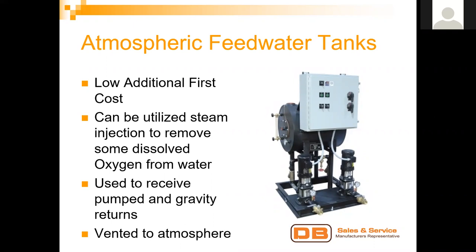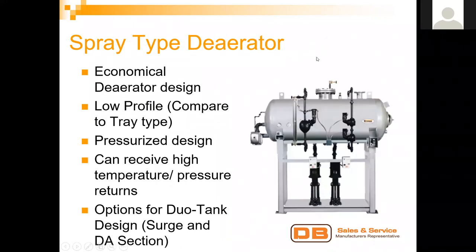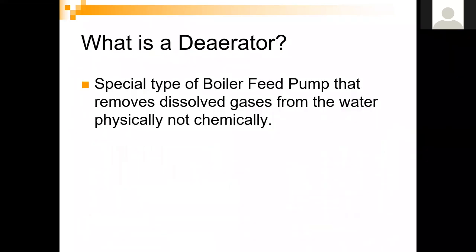A spray type deaerator is an economical deaerator design with a lower profile than a tray type. Typically a pressurized design, but atmospheric types are also available. It can receive high temperature and pressure returns, and there are options for duo-tank designs combining a surge and deaerator section in one pressure vessel. A deaerator is a special boiler feed system that removes dissolved gases from the water physically, not chemically.